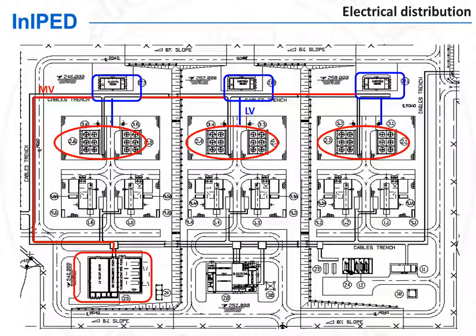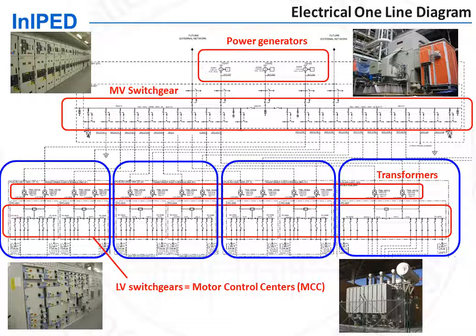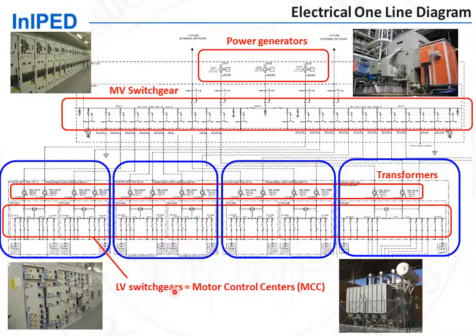This distribution is shown on the electrical single line diagram. The electrical single line diagram shows all the electrical equipment and their geographic location. It includes the power generators, which produce power in medium voltage, so they are connected with a medium voltage switchgear, typically 10 kV. Then the transformers from 10 kV to 400 volts, and then the low voltage switchgears or motor control centers. The electrical substations are also shown on the single line diagram.